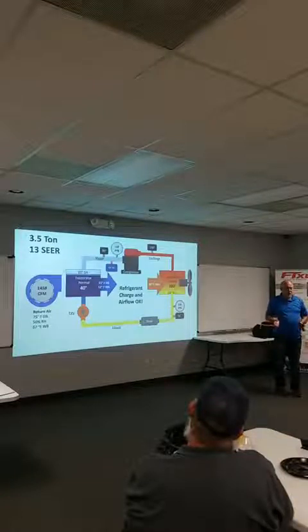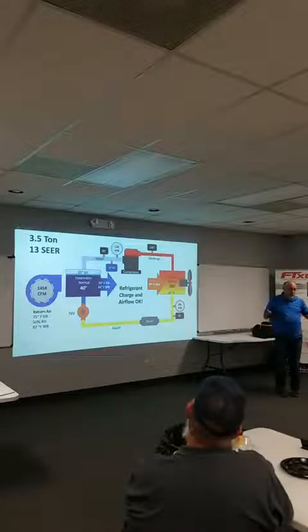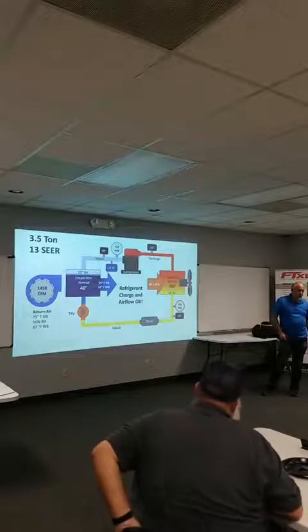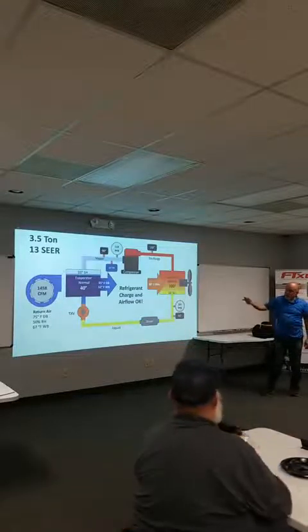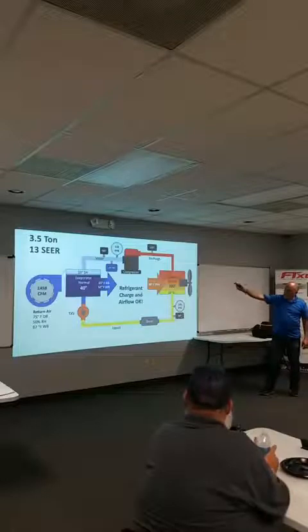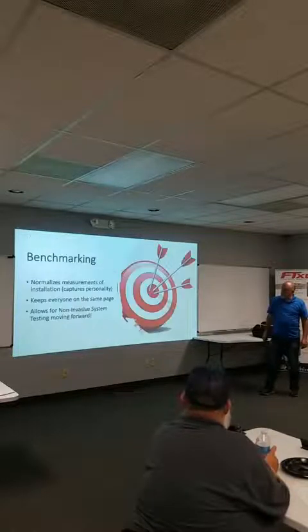insulate the suction line, right? Because somebody had run it through and nobody put enough, it was under insulated in a lot of spots, missing insulation. Or buried underground. Well, anything, like water will do that too, you'll see all of that. But it goes back to testing the system. Now, what we wanna do is when we get the system done, we're gonna benchmark it.